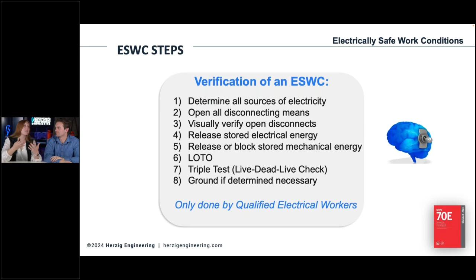Okay. Only done by qualified persons. There's a difference between authorized and qualified. I've seen plenty of authorized personnel who are not qualified. All qualified personnel have to be authorized. So if you know LOTO terms, authorized, affected, qualified versus unqualified kind of goes in a similar fashion. So authorized personnel can lock and tag out equipment, but unless they're also qualified, they can't do the triple test for the live dead live check to verify an electrically safe work condition. Hopefully I'm not talking too much in circles and confusing you, but they are two separate things. All qualified persons have to be authorized for LOTO though. That's why this does tie hand in hand in your safety program.